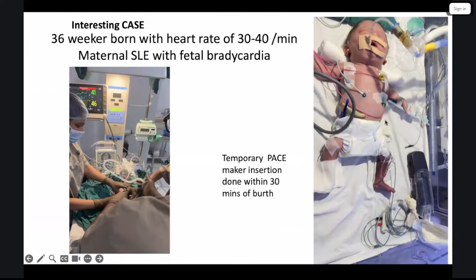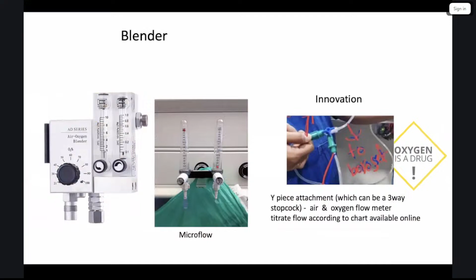Oxygen blending and microflow innovation. This emphasizes the critical concept that oxygen is a drug and must be precisely dosed to avoid toxicity in neonates. The blender here shows a standard air oxygen blender used to mix gases to a specific FiO2. It shows a microflow setup using a Y-piece attachment or a three-way stopcock. This allows the clinician to titrate oxygen and air flows manually using the flow meters and a titration chart, providing a cost-effective way to deliver precise oxygen concentrations in resource-limited settings.